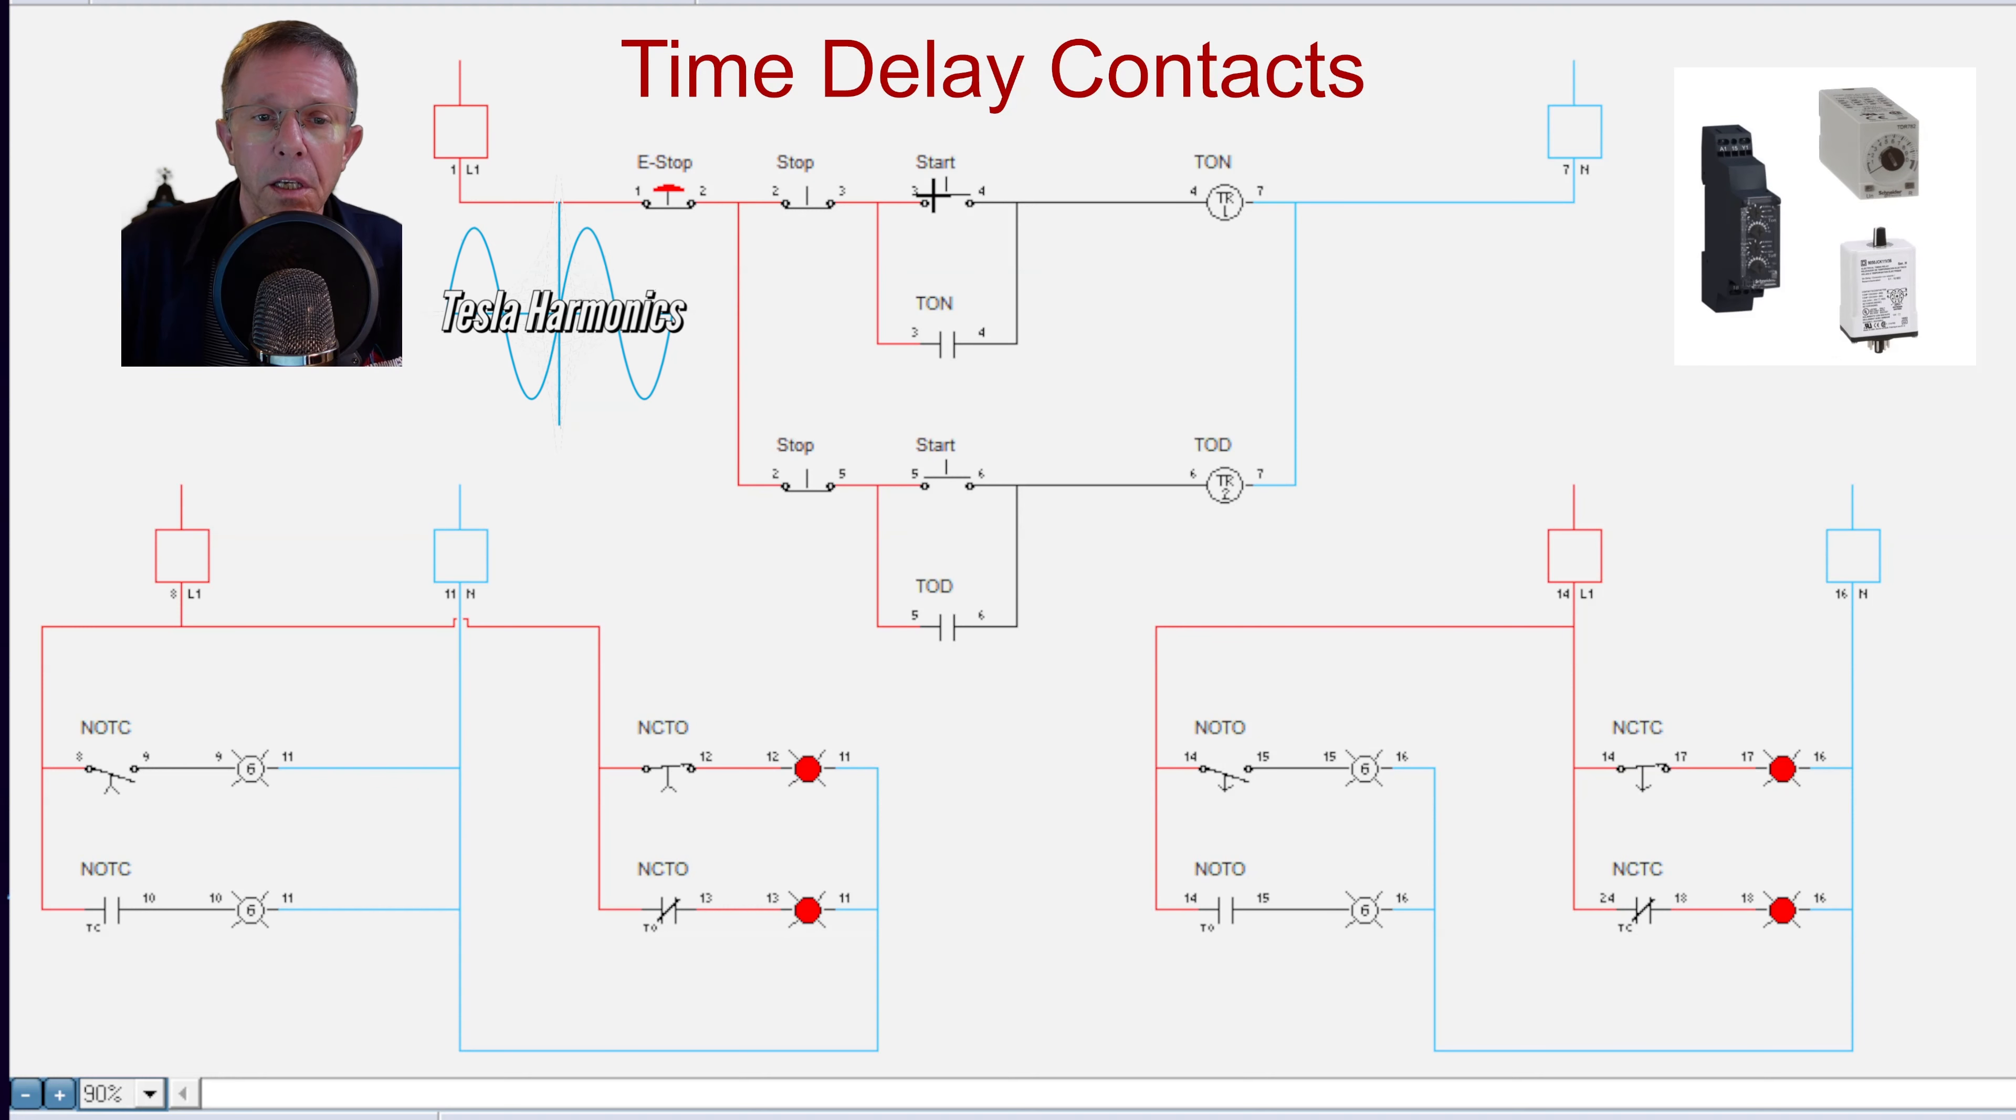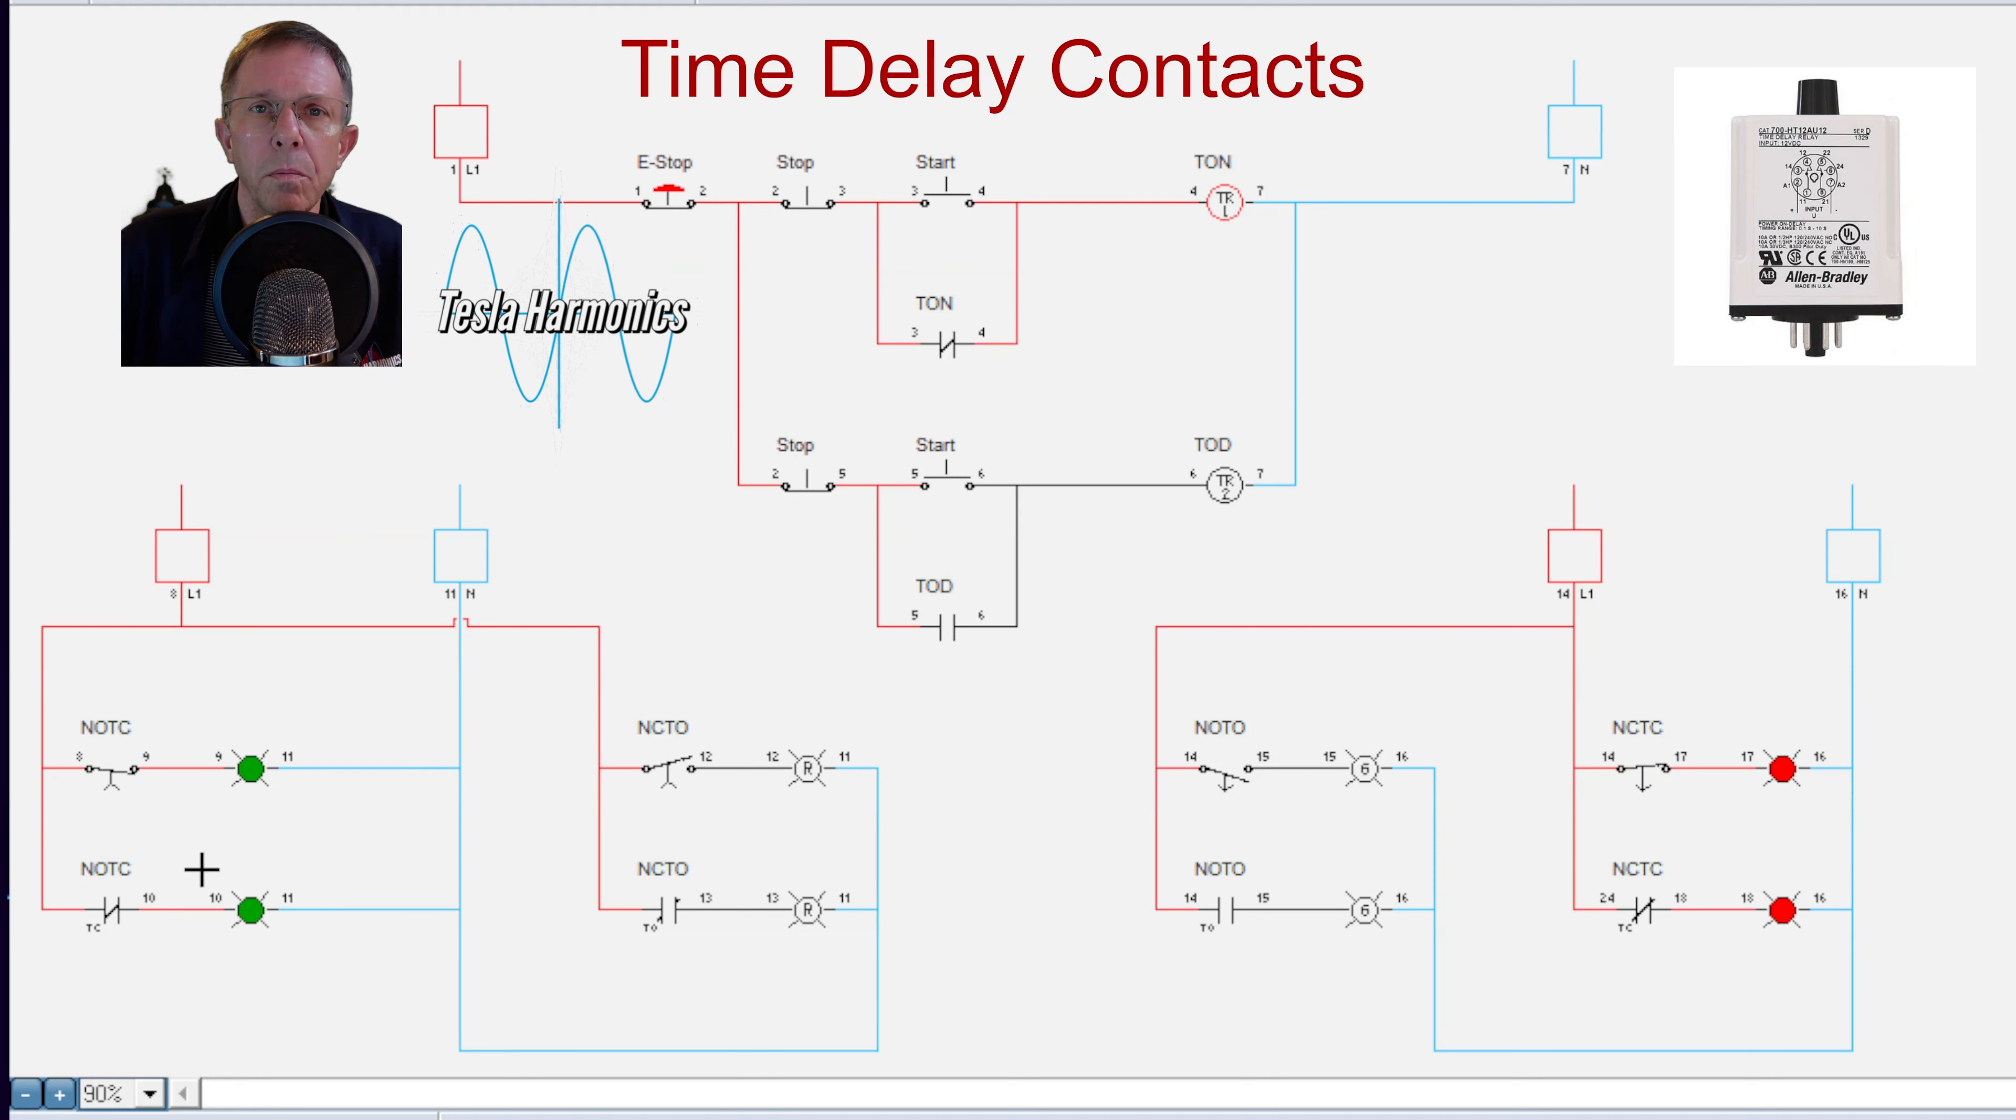If we hit start and energize that coil, it counts one, two, three, closes the two open ones and turns on the green light, opens the two closed ones and turns off the red one.